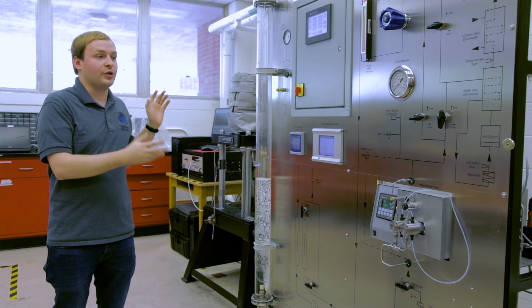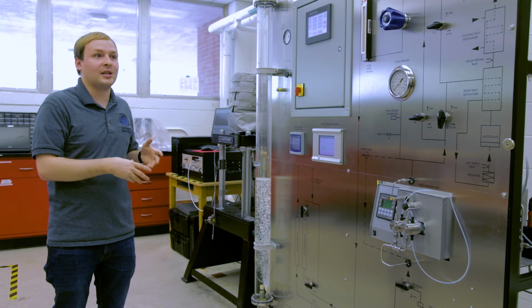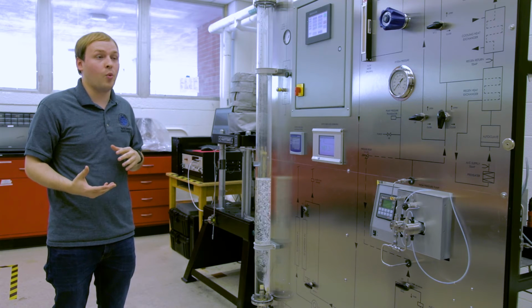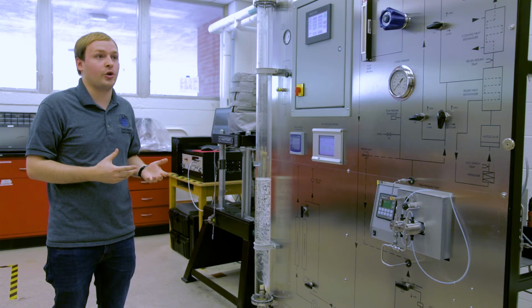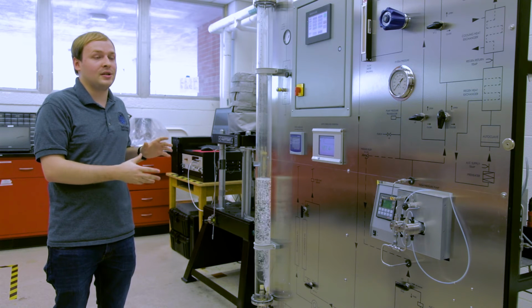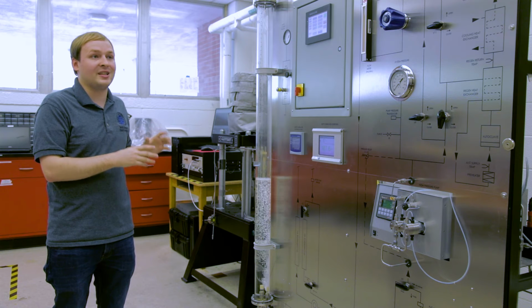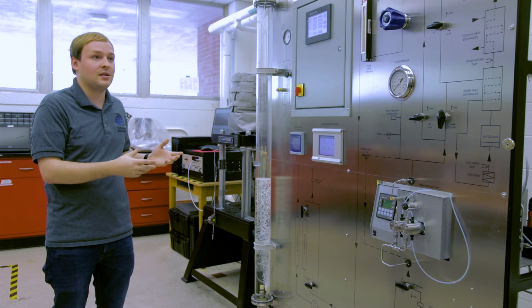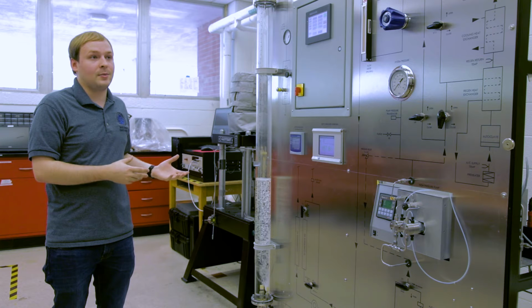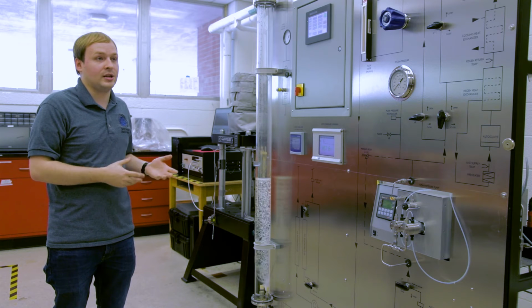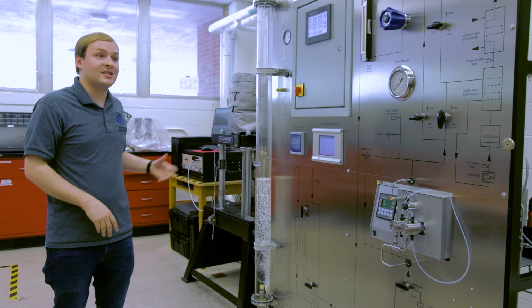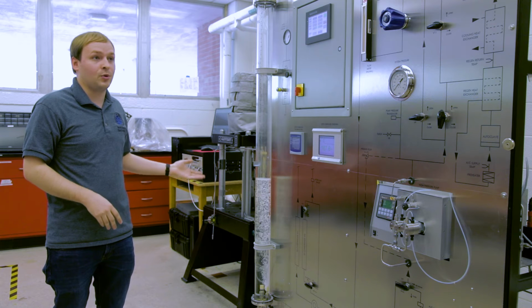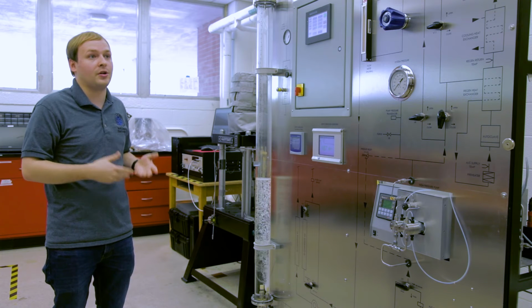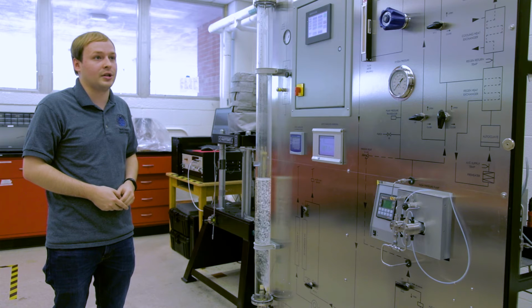I'm here to present our recirculating loop autoclave, which allows us to simulate both boiling water reactor conditions and pressurized water conditions. And what we can do with this is monitor the water chemistry at the same time as we're running our tests. We can add various dissolved chemicals such as lithium hydroxide, potassium hydroxide, or boric acid, as well as gaseous species, for example hydrogen, to hydrogenate the water as you would see in pressurized water conditions.